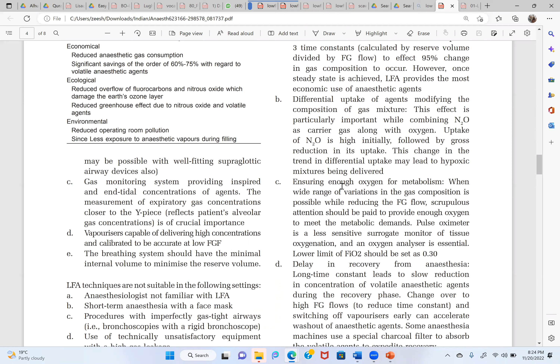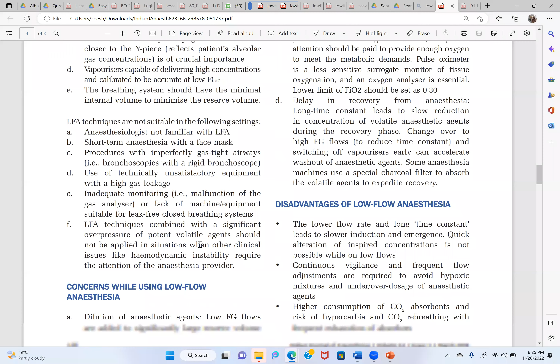They are just saying the same thing. Gas monitoring, providing inspired and end-tidal concentration of agents, and vaporizers capable. Yes. Another thing is that usually vaporizers are calibrated to a wide range of flow, but we have to make sure that the vaporizer is properly calibrated to low flow, because otherwise they will not be able to deliver accurately the fraction which they are delivering. The breathing system should have the minimum internal volume to minimize the reserve volume.